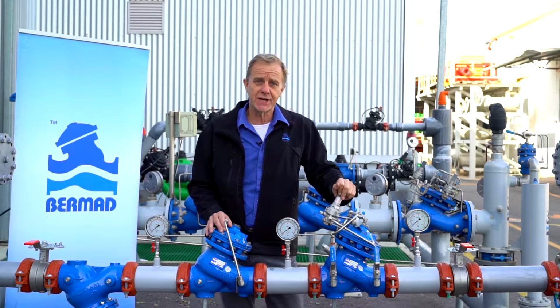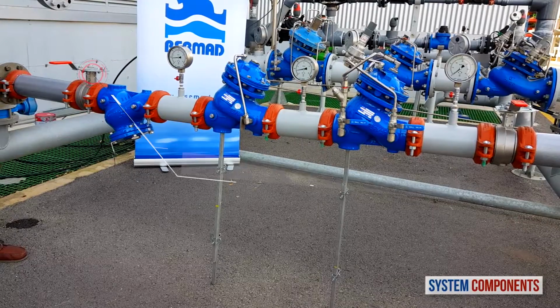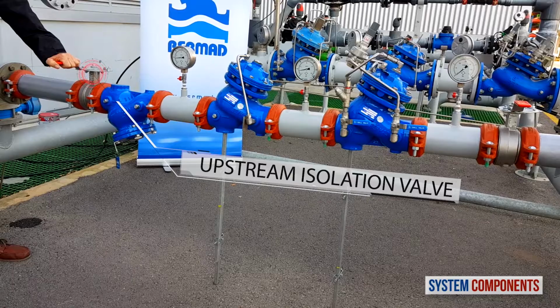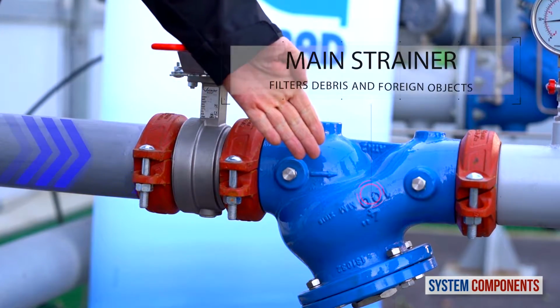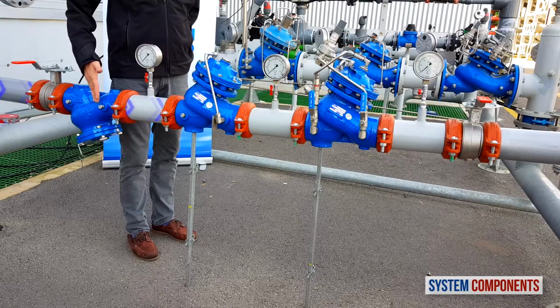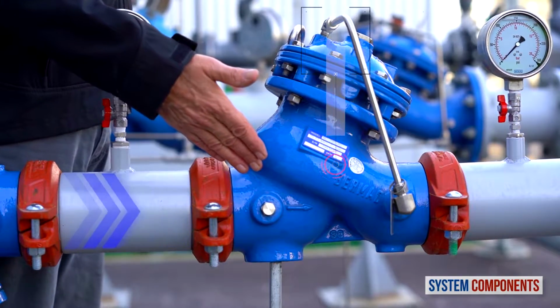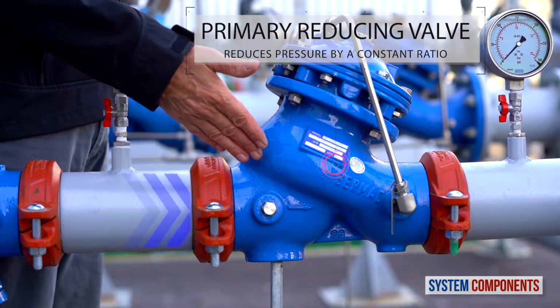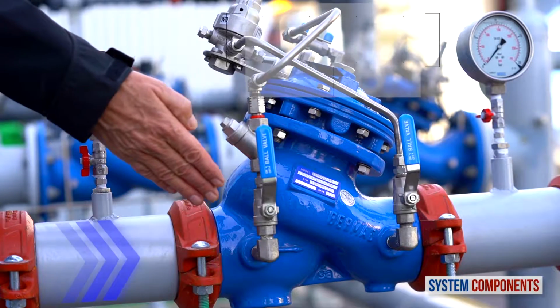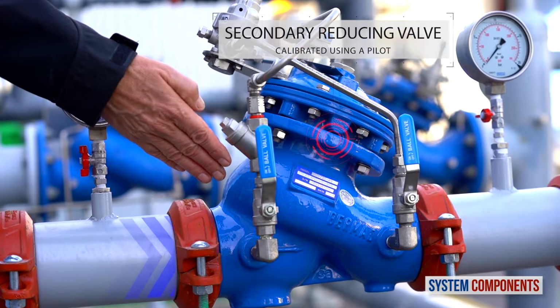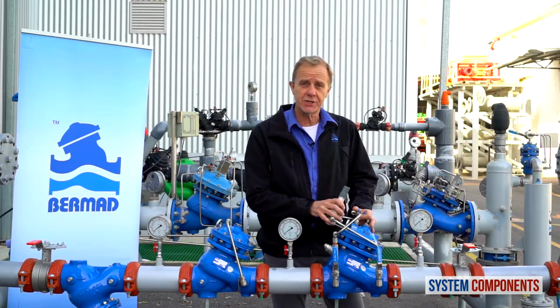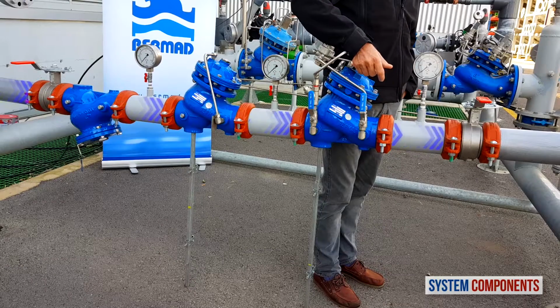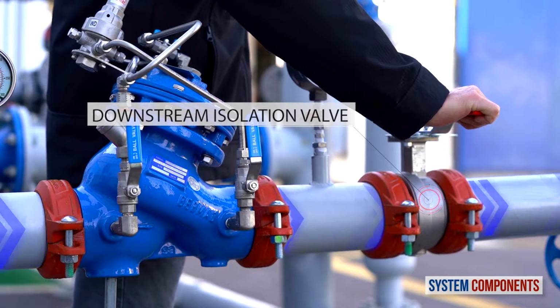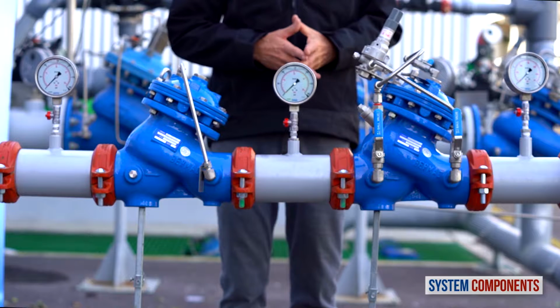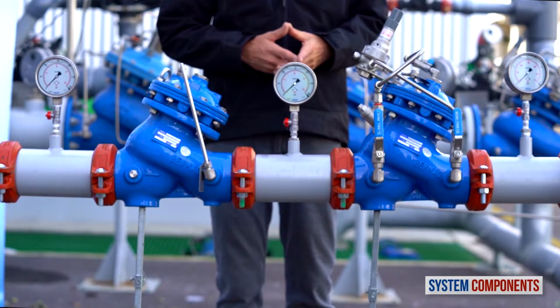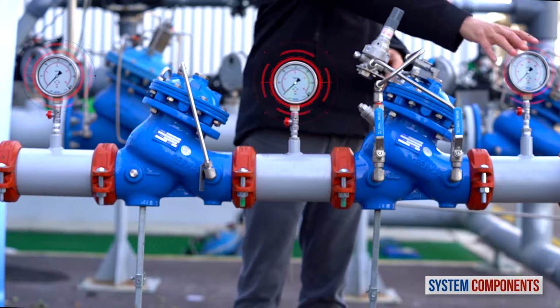Before we begin, I'd like to present the major components of this station. When the upstream isolation valve is open, water first encounters the main strainer, trapping any debris or foreign objects. The water then enters the primary proportional pressure reducing valve that reduces the pressure by a constant ratio. The water then enters the secondary or pilot operated reducing valve. It is with this valve that we can adjust the downstream pressure to the exact pressure requirement. At this point, if the downstream isolation valve is open, the water will go on to the consumer. Also, in this installation, we have three pressure gauges, upstream and downstream of each pressure reducing valve.